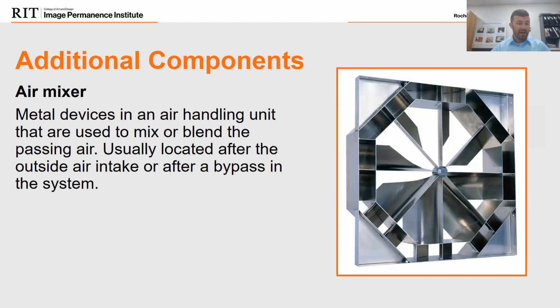Another component could be an air mixer. Though this looks like a fan, it's a stationary item. We've also seen some that look like big spaghetti strainers. The intent of this air mixer is to really help the outside air and the return air blend together. So as they go through it, there's a better blend or mix of air on the other side, and there's not spots or dead spots of more return air or more outside air. This makes sure that blend is exactly that 73 degrees coming out of this, as we showed in the example.